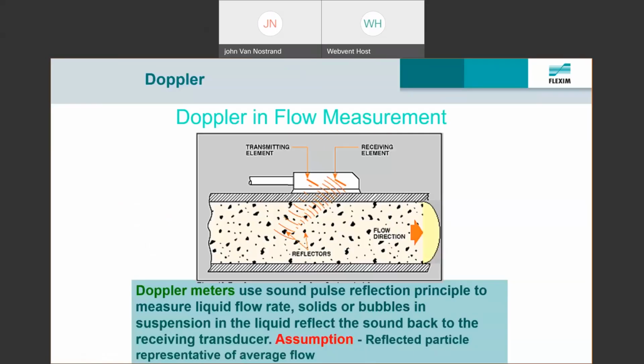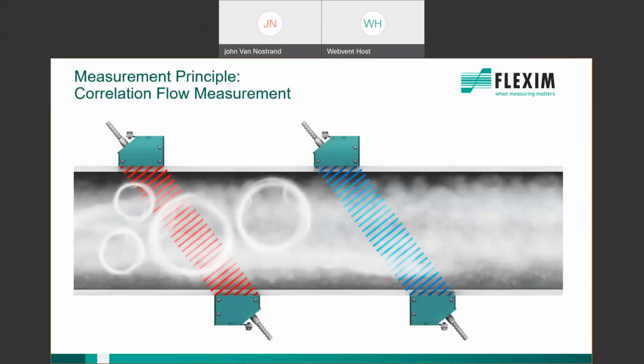We're also capable of measuring with Doppler. We have the capability of doing that, and we can switch from transit time to Doppler if needed, both measurements using the same transducer. But like I said, it's not that common that we need to do that.